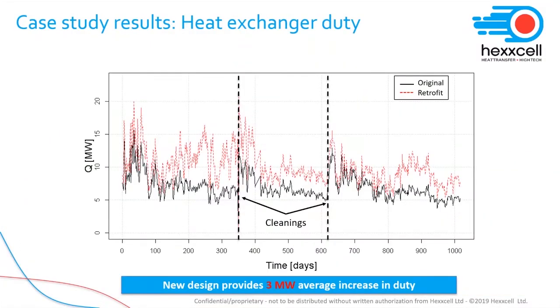What I'm showing here is the comparison between the duties of the two designs. The black line is the original configuration, 4-pass 1-inch tube, and the red line is the proposed retrofit with 2-pass 3/4 of an inch tubes. You can also see here that there have been some cleaning actions which have also been seamlessly simulated. It's interesting to see how the performance of the two designs changes over time and diverges as fouling builds up. This shows that the proposed retrofit is more resilient to the buildup of fouling in terms of its thermal performance.